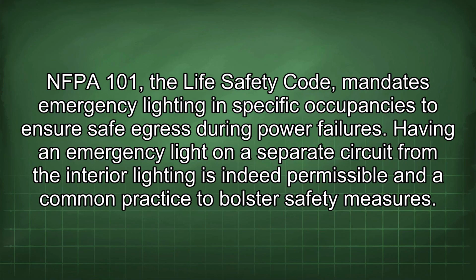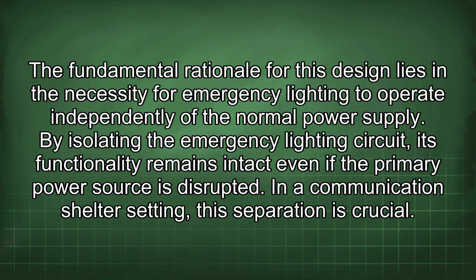NFPA 101, the Life Safety Code, mandates emergency lighting in specific occupancies to ensure safe egress during power failures. Having an emergency light on a separate circuit from the interior lighting is indeed permissible and a common practice to bolster safety measures. The fundamental rationale for this design lies in the necessity for emergency lighting to operate independently of the normal power supply. By isolating the emergency lighting circuit, its functionality remains intact even if the primary power source is disrupted. In a communication shelter setting, the separation is crucial.